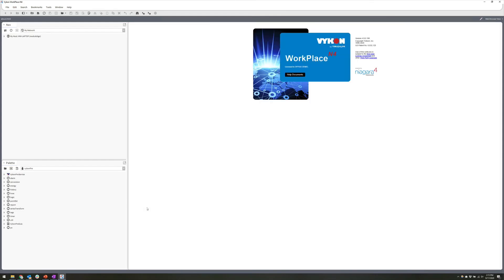Coming down to the very bottom of the file, at line 404, we have niagara.ModuleVerificationMode equals medium. At the beginning you'll see a pound sign — that means it's a comment, so we can remove it to uncomment the line. I want to move it down to low because I want to be able to use that TCOM driver. So I'll type in low, do a save, and close out. With Workbench open, I can go back into my palettes and pull up the TCOM module, and you'll see the module now opens up without any problems.